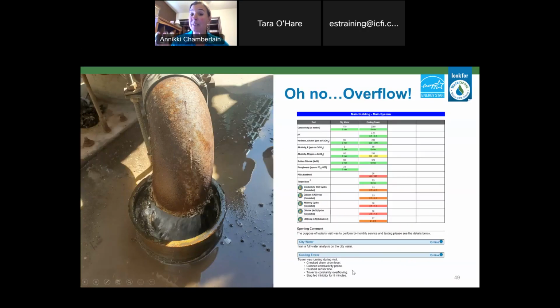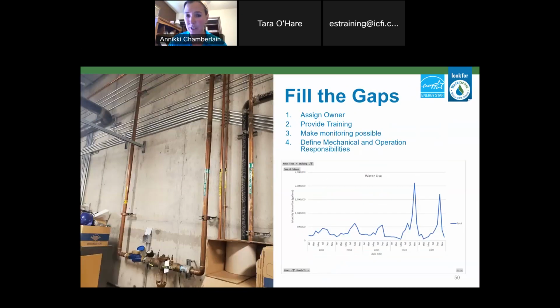So what this shows me is there's a gap. The service provider is telling him that there's overflow, but maybe there's no tower manager that's actually reading the reports. Plus there's a gap here in that the water treatment person isn't responsible for the mechanical adjustments. So who is responsible for those mechanical adjustments? Going back and looking at their water use, I see, dang, they've got these big spikes that happen over time. So this property would definitely benefit.